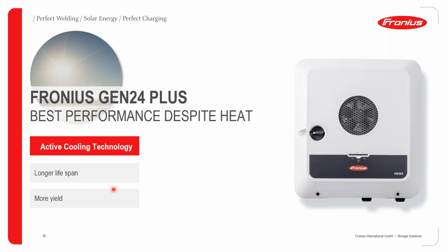By the use of the active cooling technology in the Fronius Gen 24 inverters, we are also guaranteeing you more yield for your systems. Especially, this is very ideal for the African market, where we have some regions with very high ambient temperatures. Some regions do get average 35 to 40 degrees ambient temperatures. So when you have these kind of situations, most inverters that are passively cooled will start to derate at some point, and some of them will actually derate at as low as 30 degrees ambient temperature. But with a Fronius inverter that is actively cooled, the derating behavior will happen much later on, at almost 50 or 55 degrees ambient temperature. So that guarantees you a lot more yield.